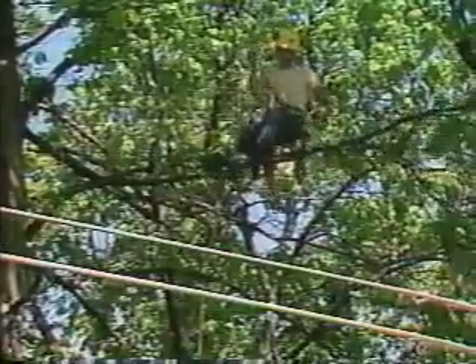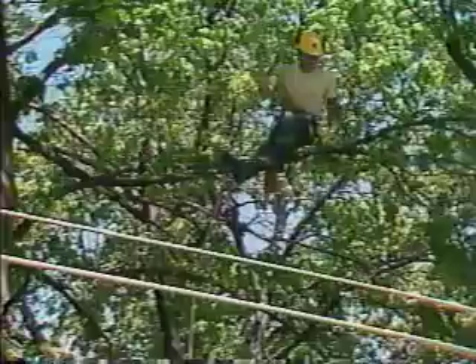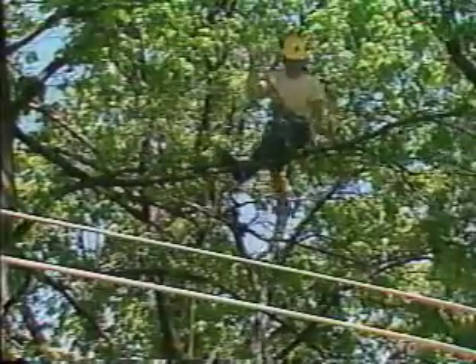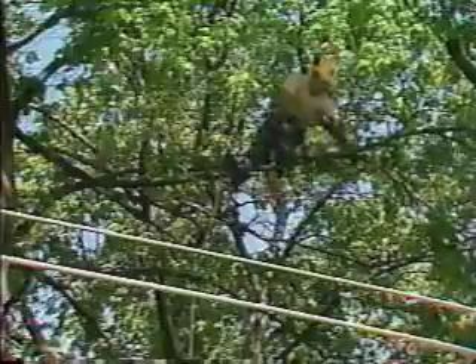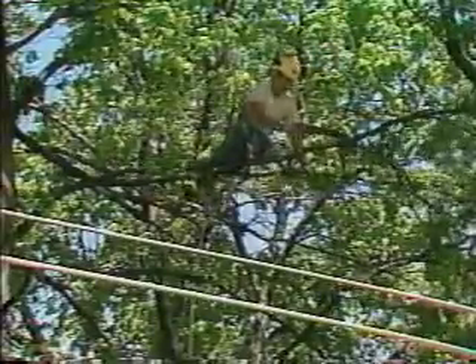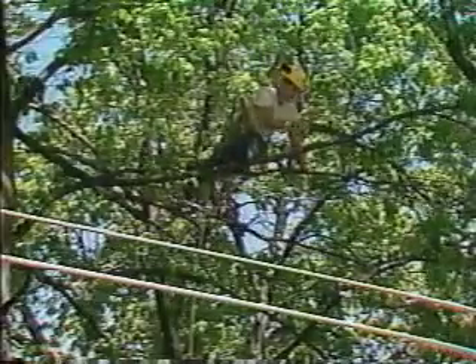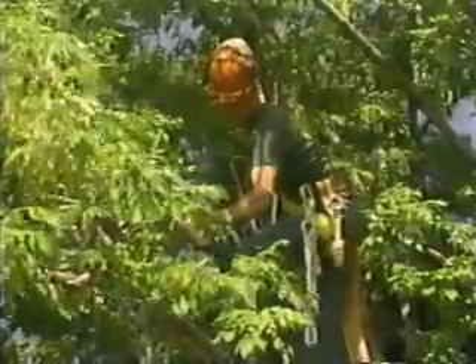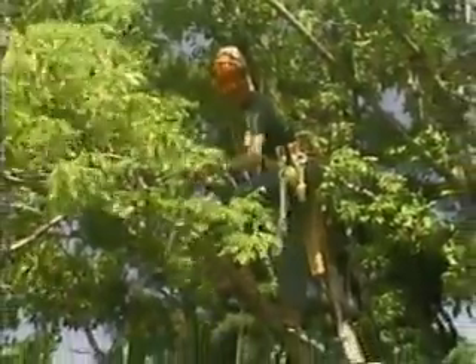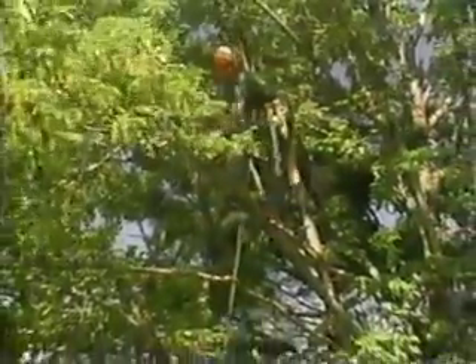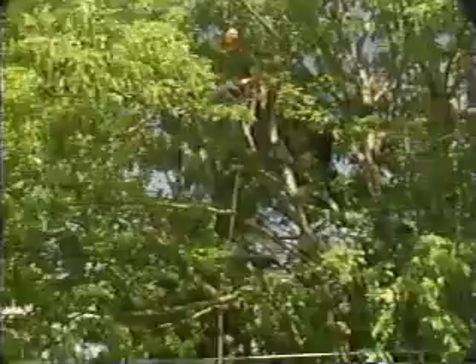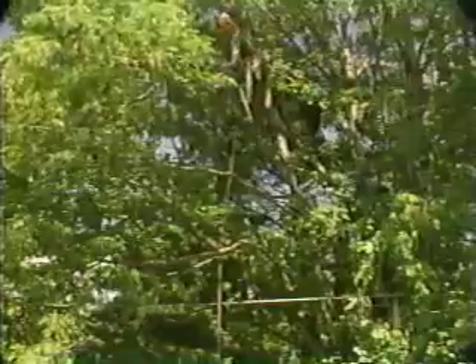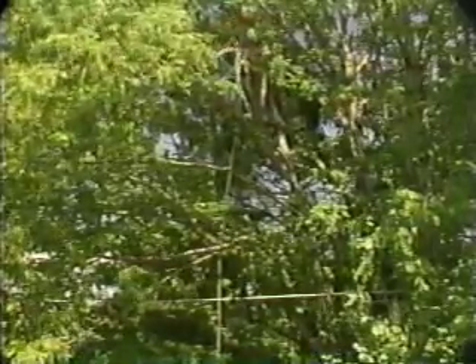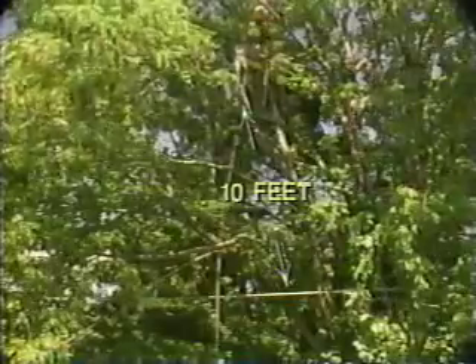Safety regulations state that there shall be a minimum working distance for those trained to work near electrical hazards of 2 feet 4 inches from any line energized in excess of 1,100 volts, with the work distance increasing as the voltage increases above 15 kV. This chart specifies the minimum separation requirements based on varying voltage. For the tree worker trained to work near electrical conductors, maintaining as great a distance as possible from distribution lines provides a good margin of safety. All workers not specifically trained to work around electrical conductors must maintain a minimum clearance of 10 feet from distribution lines and an even greater distance from transmission lines as per the chart.